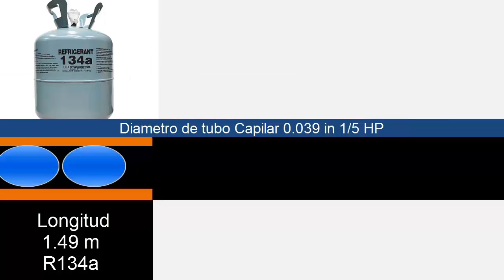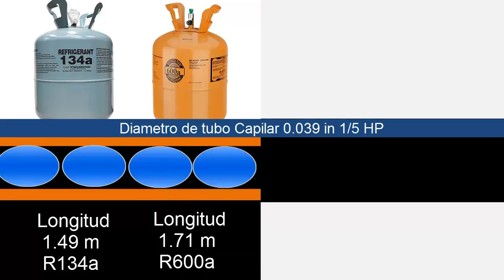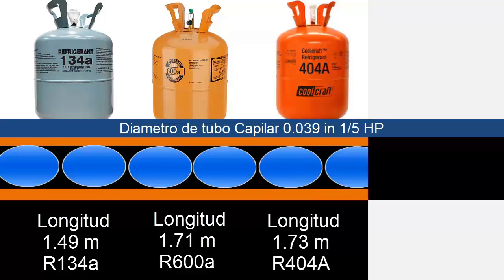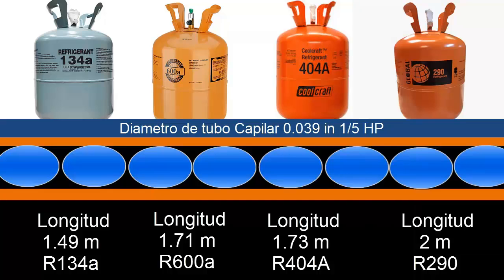Now let's move on to the power of a fifth HP. With R-134A the length must be 1.49 meters, with R-600A the length must be 1.71 meters, when we work with R-404A the length must be 1.73 meters, and when we work with R-290 the length of the capillary must be 2 meters.